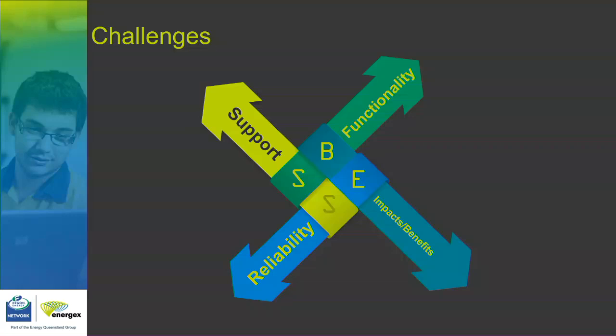Another challenge, and Paul, you were touching on this in terms of how the systems operate, being able to withstand what I would call credible contingencies. There are contingencies on the network, contingencies that occur in normal life. The systems need to be able to stay on. So for example, a quick little voltage dip, we don't want all the batteries necessarily tripping off all the time. We might want them to stay on. Or we might want it to go, yeah, I've got a battery trip, but I'm actually going to reduce my output to 0 before I trip off.